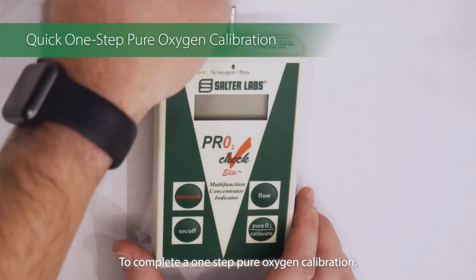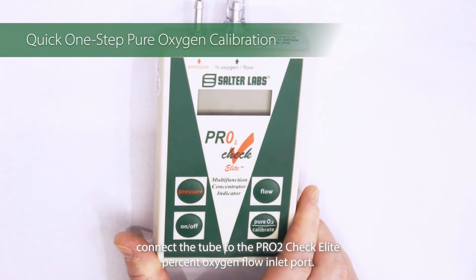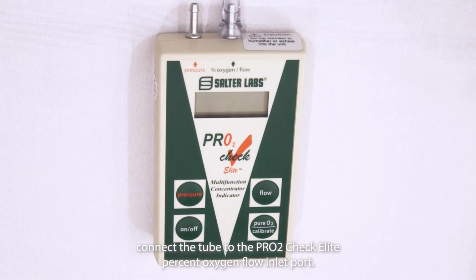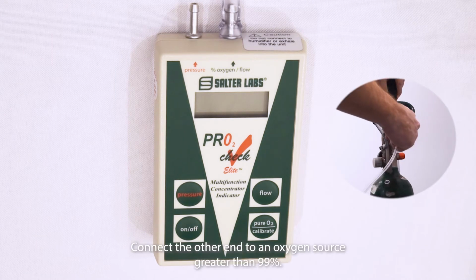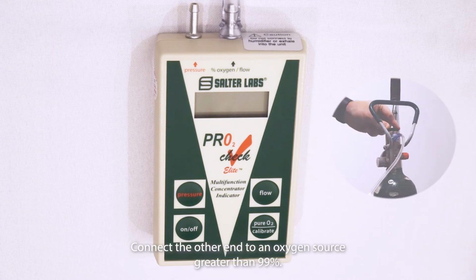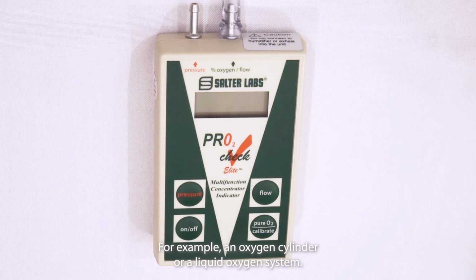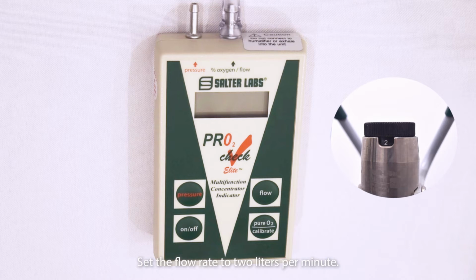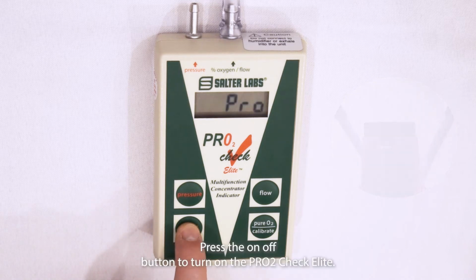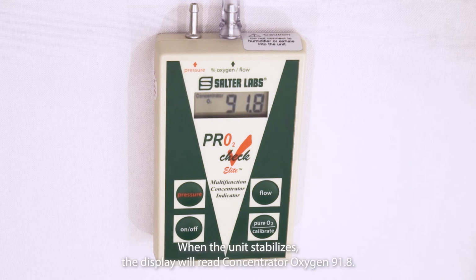To complete a one-step pure oxygen calibration, connect the tube to the PRO2 Check Elite % oxygen flow inlet port. Connect the other end to an oxygen source greater than 99%, for example, an oxygen cylinder or a liquid oxygen system. Set the flow rate to 2 liters per minute. Press the on-off button to turn on the PRO2 Check Elite. When the unit stabilizes, the display will read concentrator oxygen 91.8.